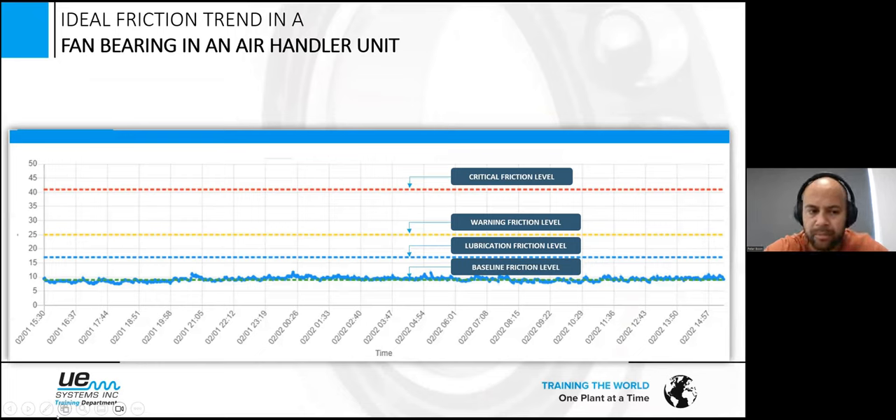You can see the green line — that's the baseline used to trend the bearings. The blue line is the lubrication line, the yellow line is plus 16 dB indicating beginning visual faults, and the red line is plus 35 dB — the severe damage phase. Here, even though the program says you need to grease the bearing, it's not needed — you're still in the healthy phase.